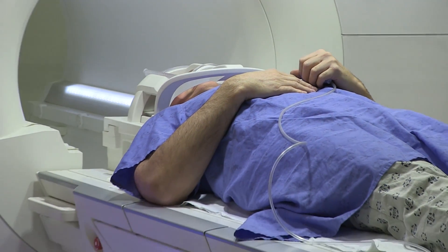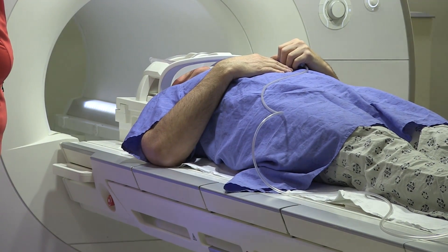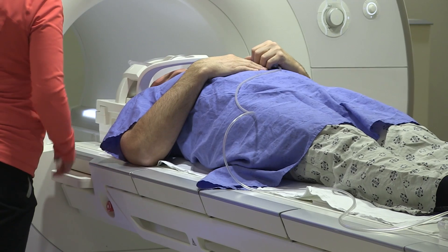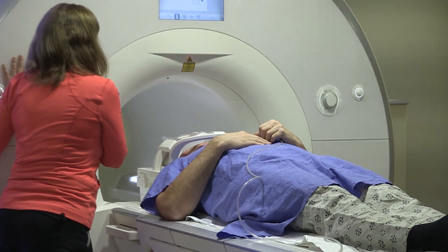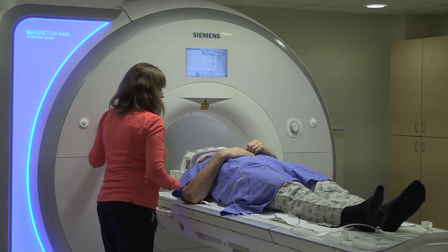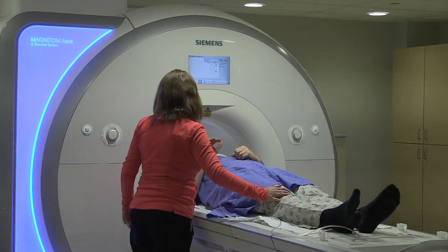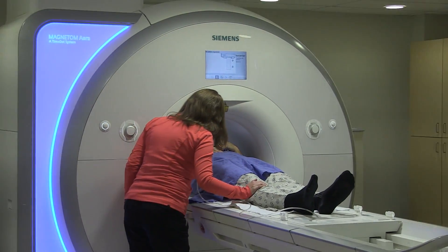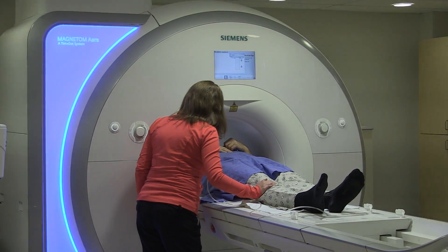The table is nearly noiseless as it elevates the patient and then draws him into the centre of the scanner. Although this appears routine, by the time the patient is relaxing, the technologist has already calculated where to position the patient. It's important to have the head in the exact centre of the magnetic field. Some last-minute instructions, and we're ready to begin what is about a 15-minute scan.